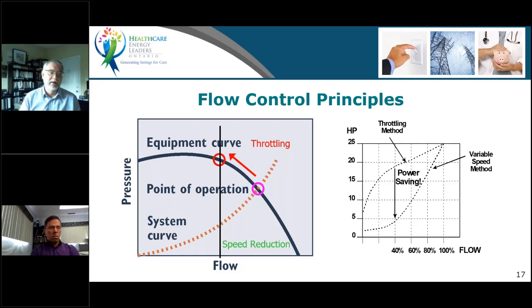But if we're throttling and we can remove the throttling by using speed reduction, that is, half speed, third speed to get half flow, quarter flow, then we would basically be moving down the system curve. And remember, the power required at the red and the green points is the flow times the pressure. So at the red point, the flow times the pressure is probably more than double what it is at the green point.